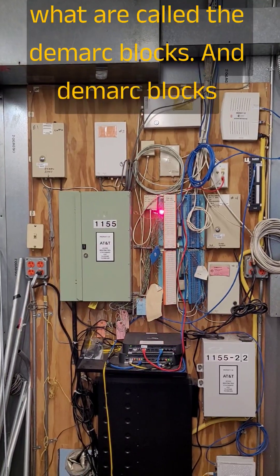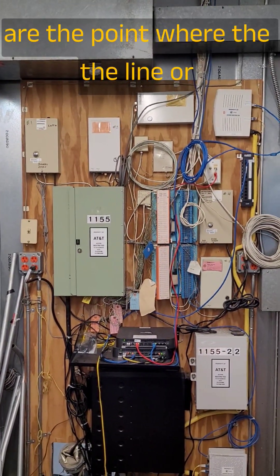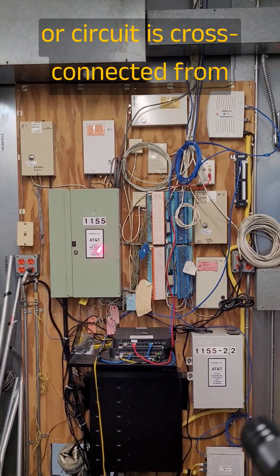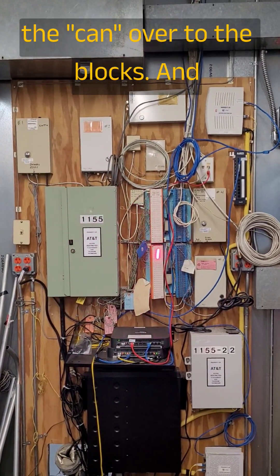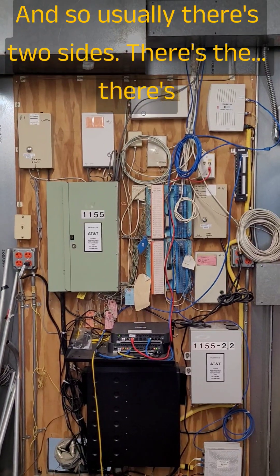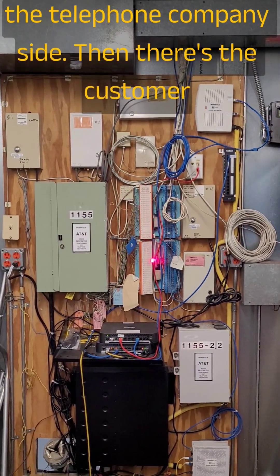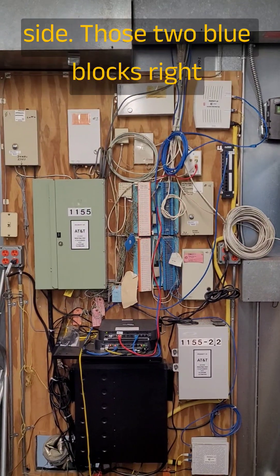Over here in the middle is what are called the demarc blocks. demarc blocks are the point where the line or circuit is cross-connected from the can over to the blocks, and that's where the service is delivered to the customer. Usually there's two sides — the telephone company side and the customer side.